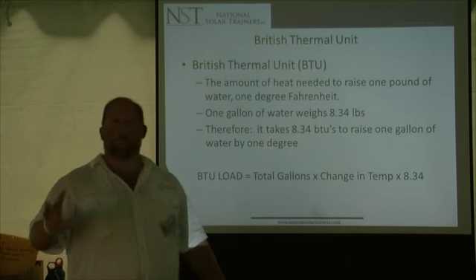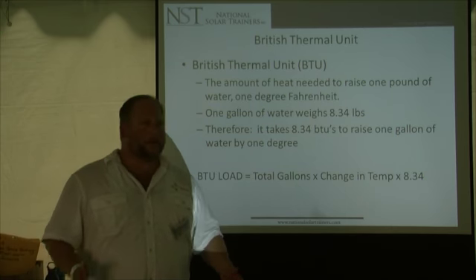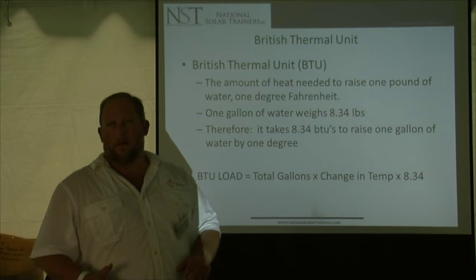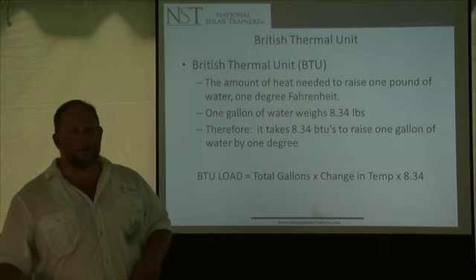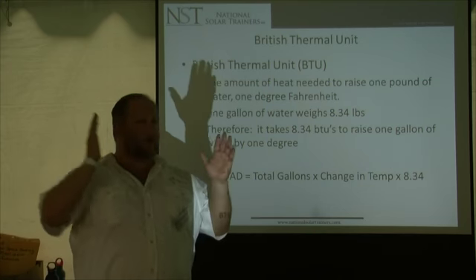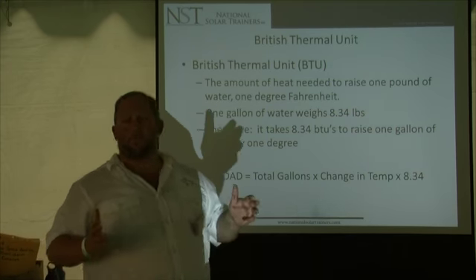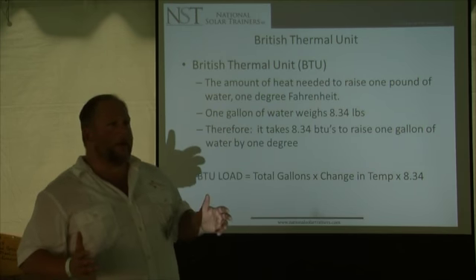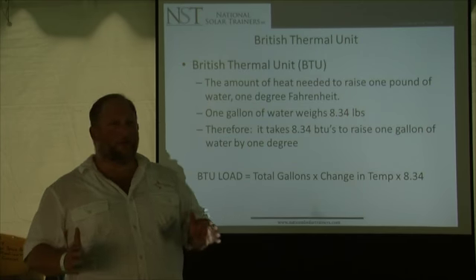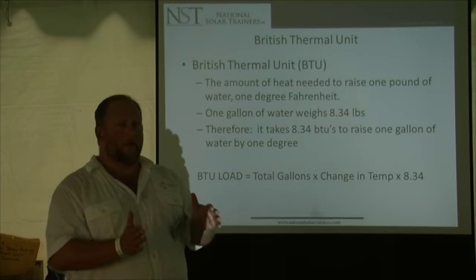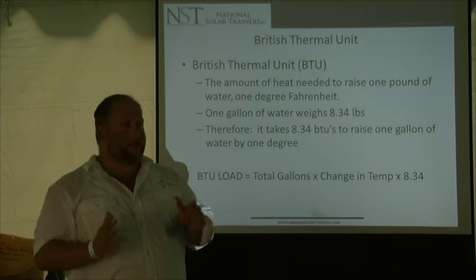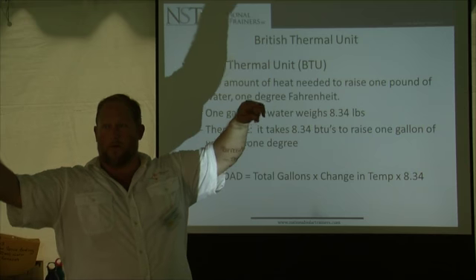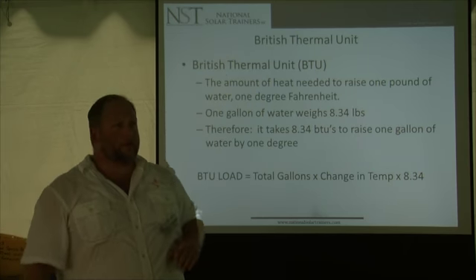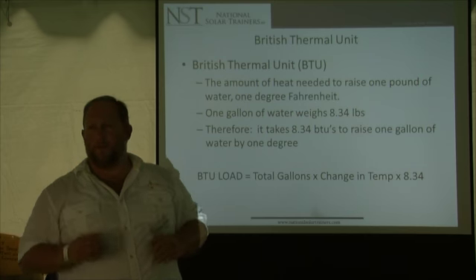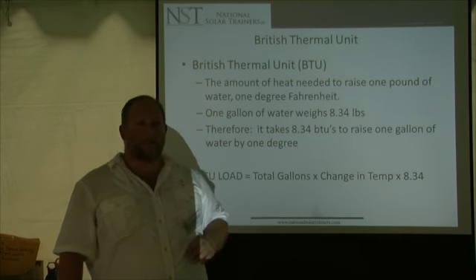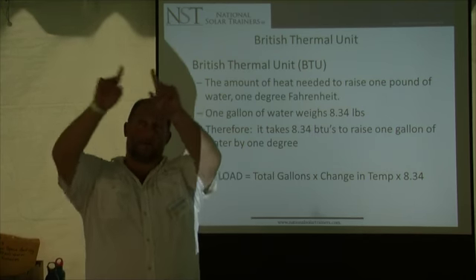Thermal - I should have started with this. We're making BTUs, it's all about BTUs. A human produces 500 BTUs an hour. The sun per square foot gives us about, right now today, probably 1,800 BTUs per square foot hitting this roof. That's a lot of BTUs. If you add up the square footage of this roof, say 200 square feet times 1,800, we're looking at 360,000 BTUs today just hitting that roof.